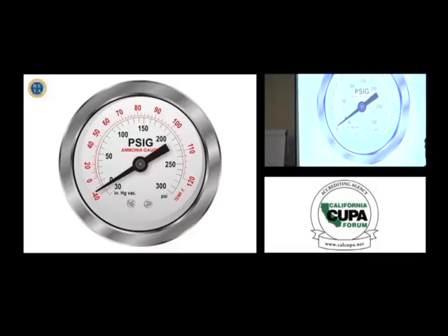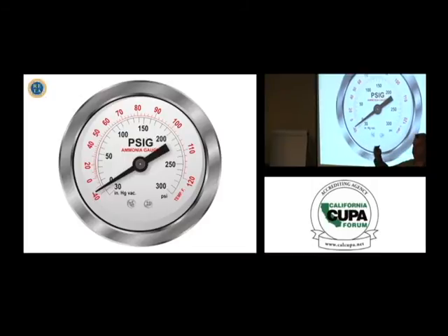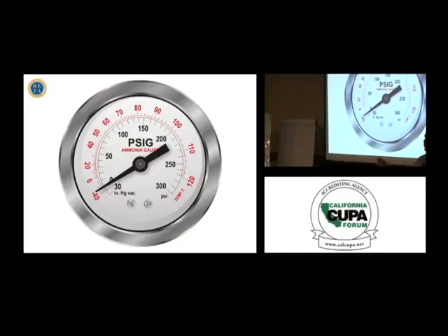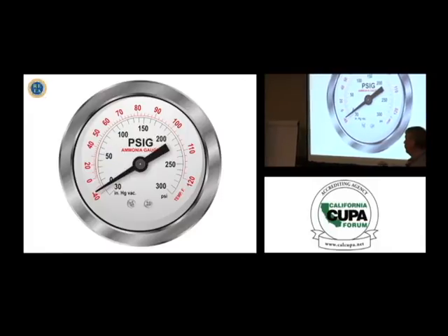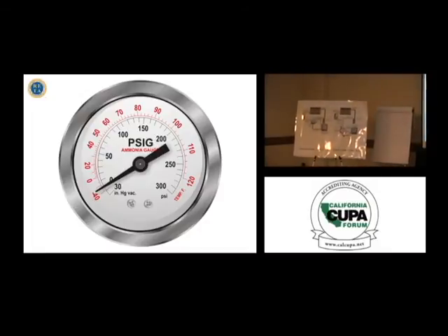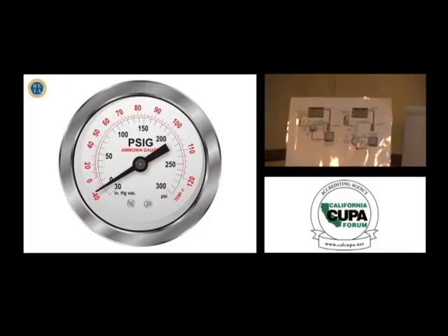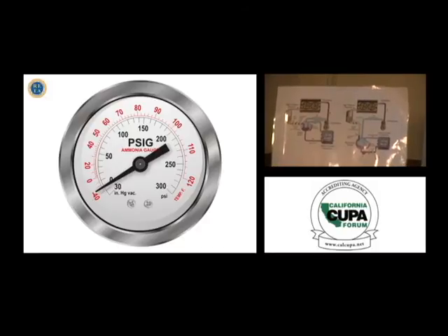In the system, you have saturation happening at 2 locations. In the evaporator, somewhere in the evaporator, you are absolutely in saturation. And also in the condenser. Those are the 2 places where you can always know that there's saturation going on, because if you don't have saturation, you're not getting the work done. Other parts of the system might be somewhere in between. It could be where the temperature of the refrigerant is higher than the pressure it's showing. That's normal, but that's a hard concept. But it is normal. And there's places where the pressure or the temperature is lower.